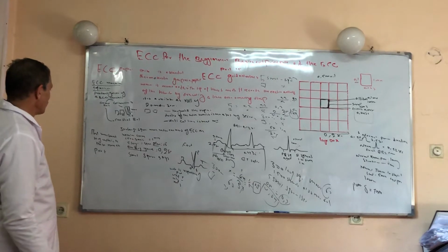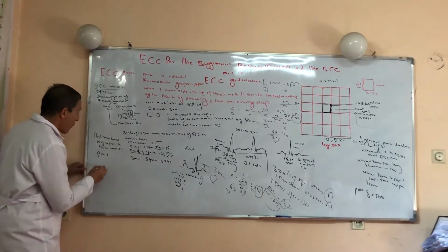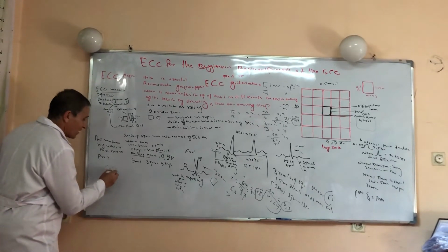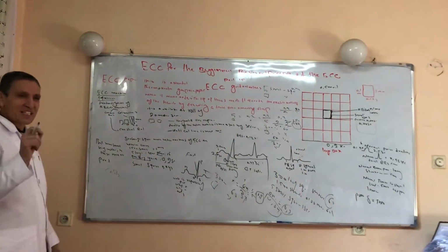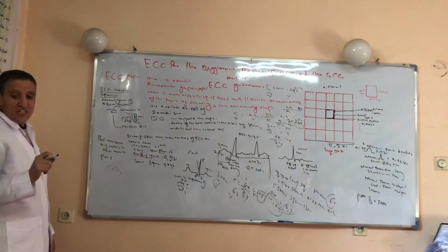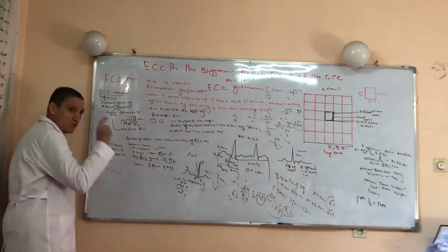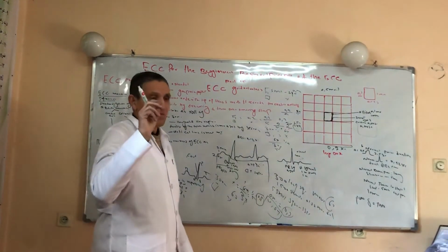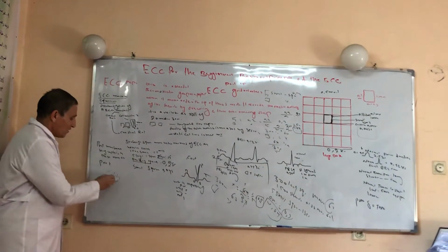Another one is the calibration signal. What does calibration signal mean? A calibration signal is defined as a standard signal of 1 millivolt. It displaces the needle of the ECG machine by 10 millimeters, or 2 large boxes, which represents 1 millivolt, or finally 1 centimeter.